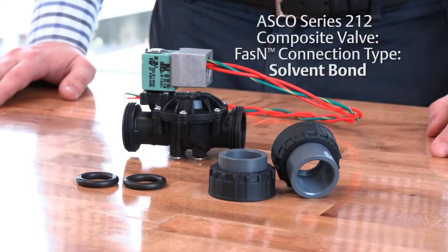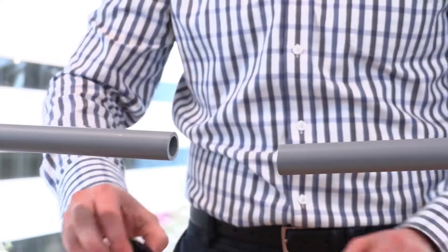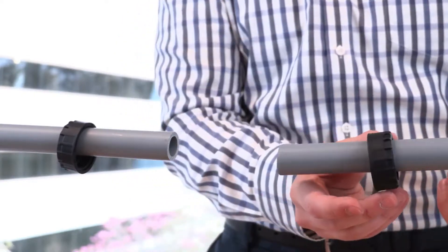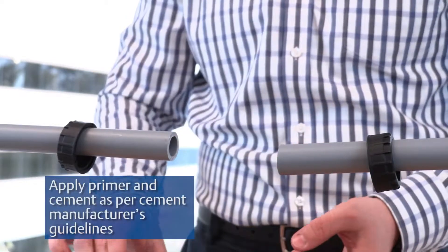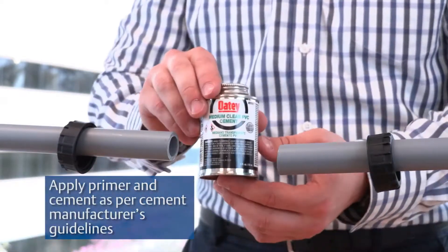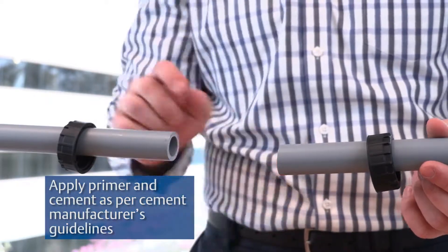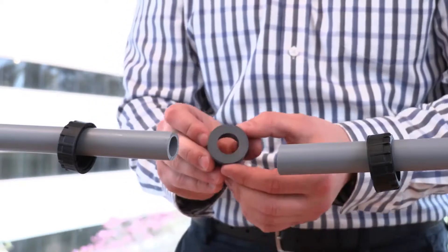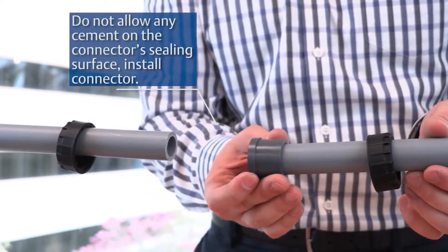FasN connection type: solvent bond. Install the outer shroud of solvent bond end connectors to the pipe. Apply primer and cement as per the cement manufacturer's guidelines. Do not allow any cement on the connector's sealing surface. Install the connector.